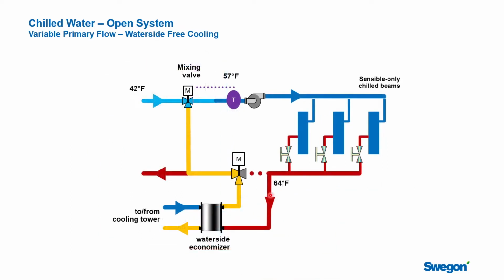So if we zero in a little bit on what's going to go on in this control sequence in here, you see we've got water coming to and from the cooling tower. We can use that to cool the water down. Our goal is to have a 57-degree supply temperature out to the chill beams. It's going to come back around 64, and then we would use the tower water to cool that back down to 57. If this actually overcooled and made the water cooler than that, you could mix some 64 degree water with that 57 degree or whatever water temperature we get from here, maybe 53 or 54, to get it back up to the 57 degrees. In the dead of winter, this thing would be 100% bypass.